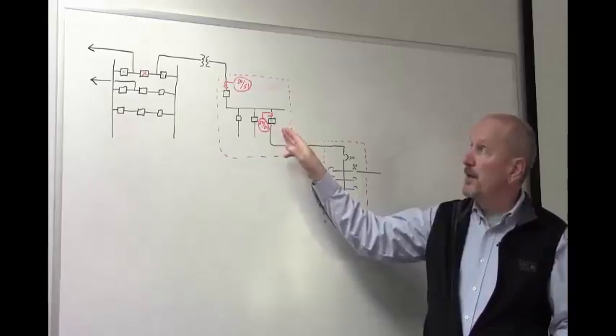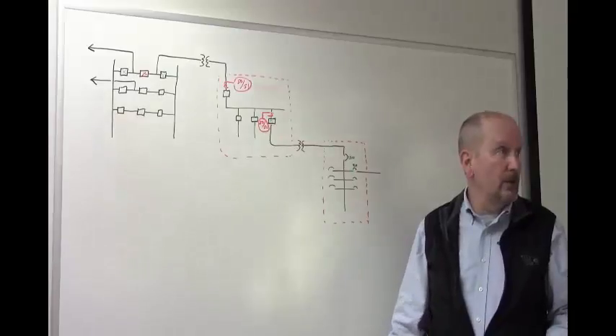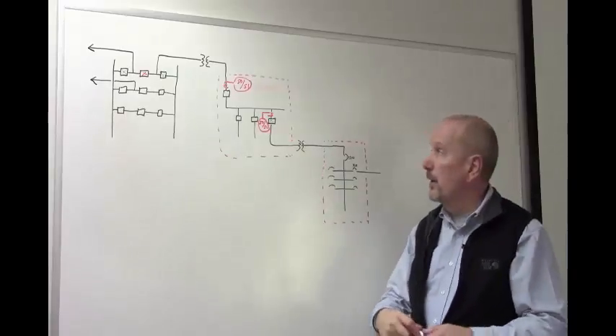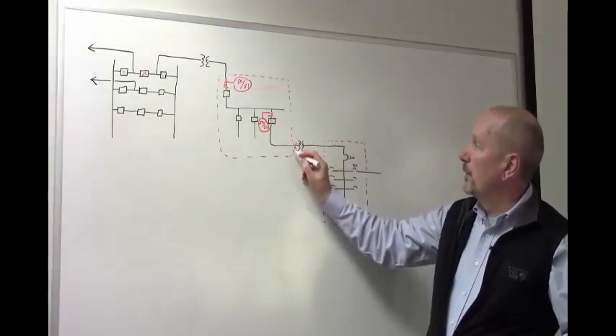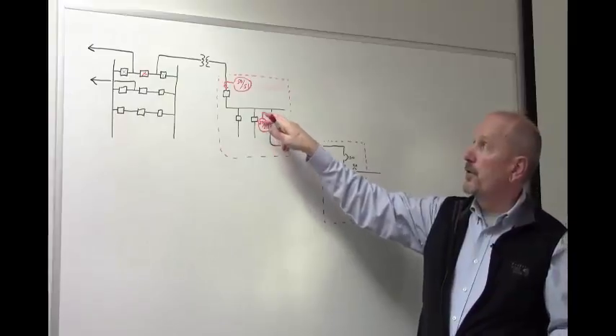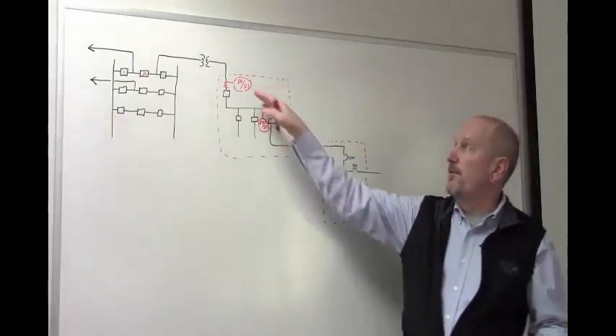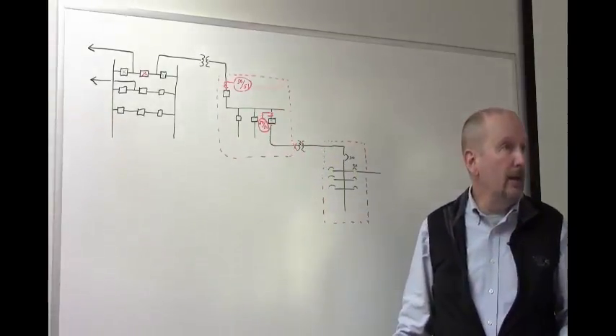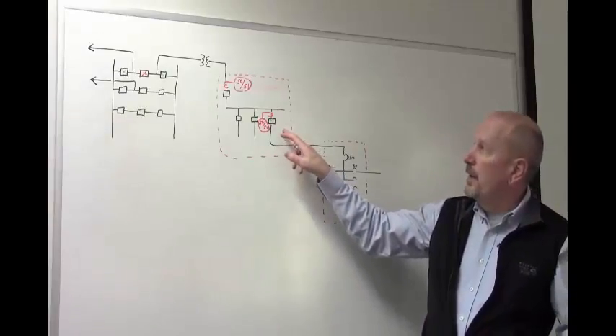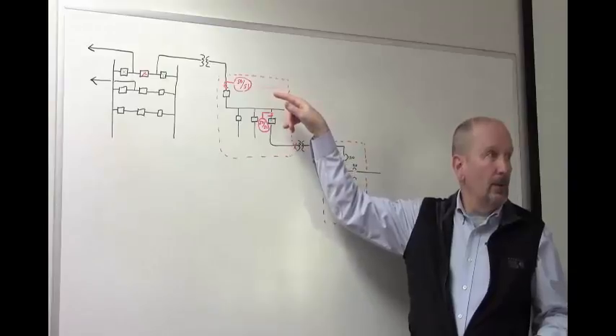Going up a level to distribution switchgear — say 12.5 kV or in the local Portland General system 13 kV — if you had a fault on a cable and the feeder breaker fails to trip, there's really nothing else that can back it up automatically. So in some fashion you've got to have a breaker back it up. The question is: how fast can that operate? With coordinated overcurrent protection, the upstream breaker has to have a slower trip than the downstream one.